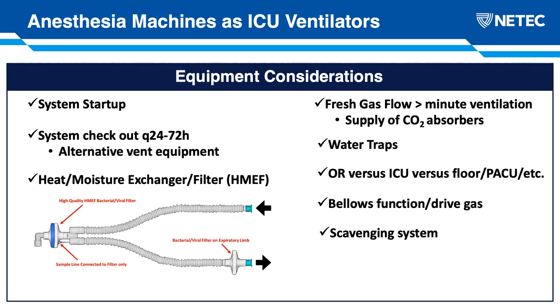As I mentioned before, if we're able to keep the fresh gas flow higher than the minute ventilation, it will reduce or eliminate the amount of rebreathing going on, which will prolong the shelf life, if you will, of the CO2 absorber that's in the system, and in many cases can be eliminated. So this will allow us not to go through that disposable, which if this happened on a mass scale would likely become a limited supply resource. We recommend adding water traps in line, and I'm sorry I don't have a picture here, but often we'll add a water trap into the circuit to catch that excess condensation and prevent it from either backing up in the circuit or making its way into the internal components.